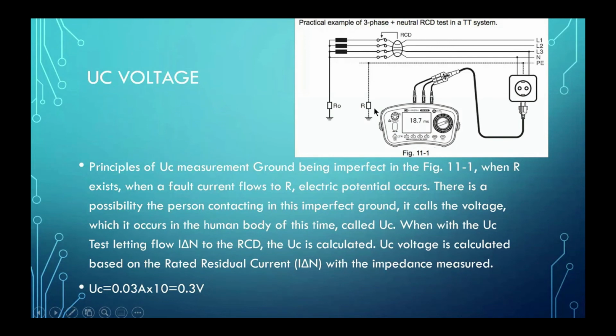Okay, to let you know before I explain more, UC voltage is a function under the RCD test. Later I will show you the test. Then I proceed. If a fault current happens in this local earth, an electric potential may occur. There is a voltage, so there is a current flow. There is a possibility a person goes and contacts this imperfect ground. This voltage is called Uc, called touch voltage. Understand?